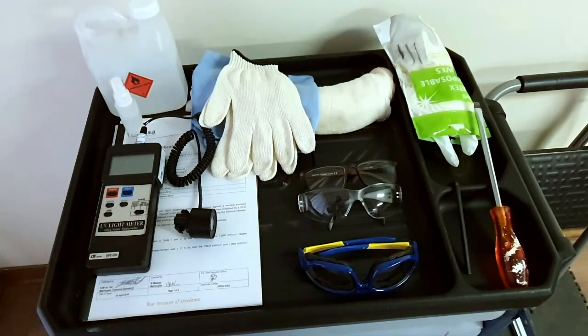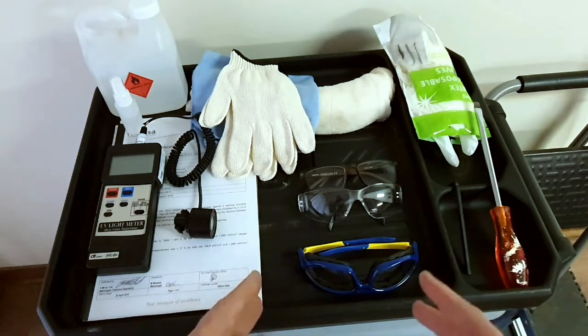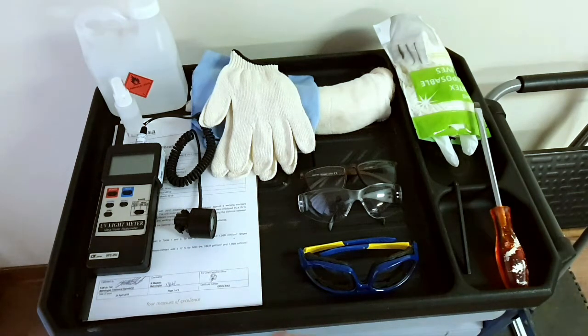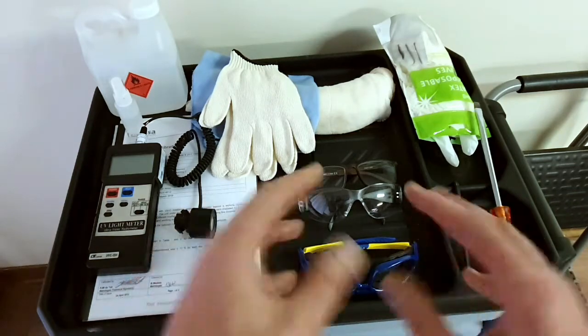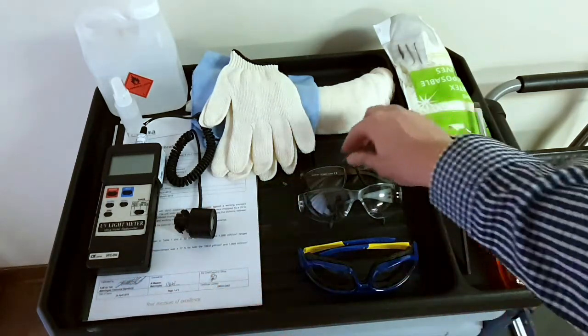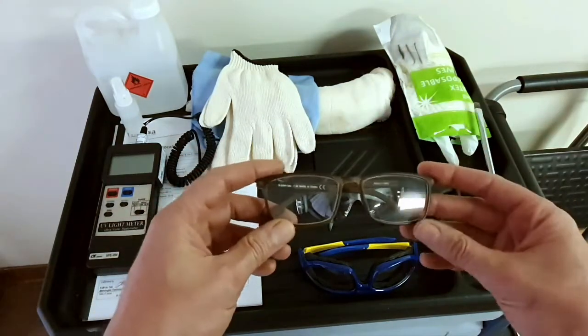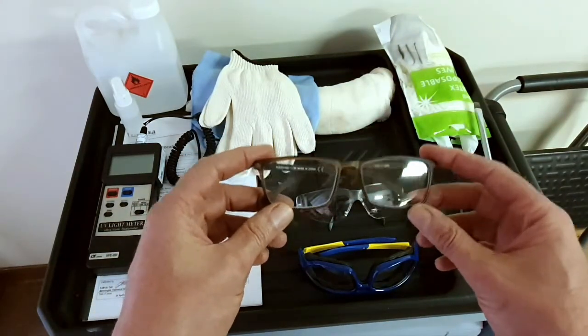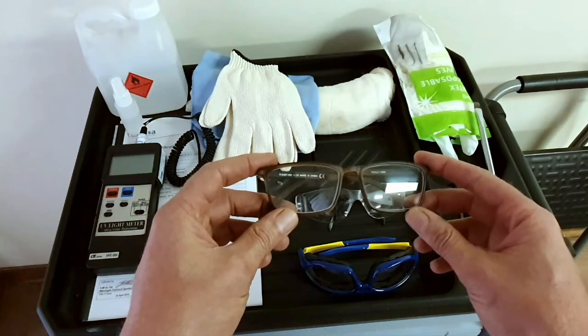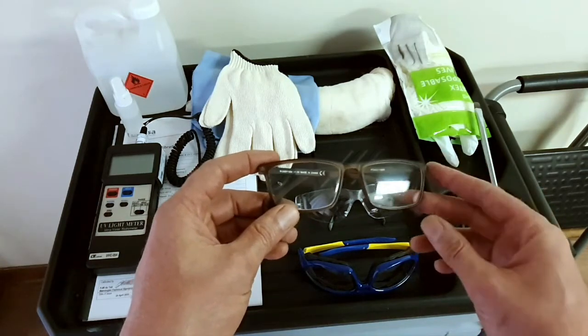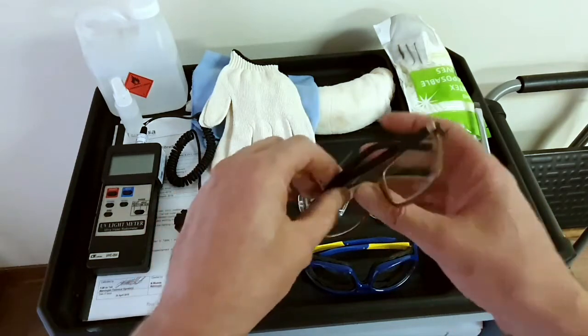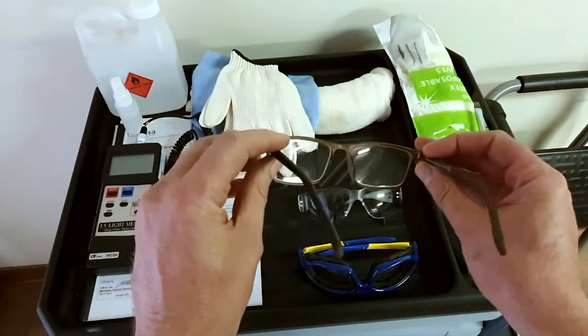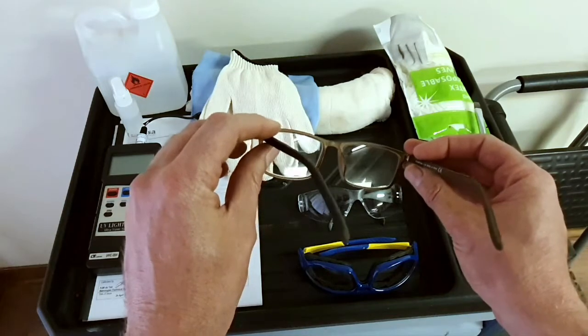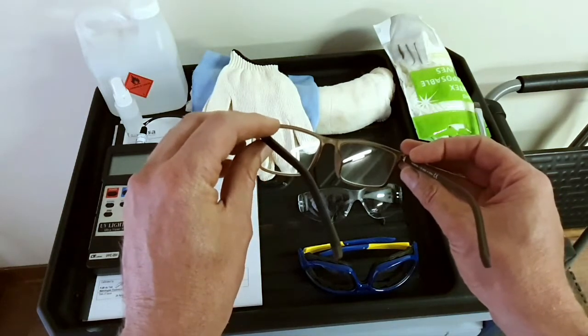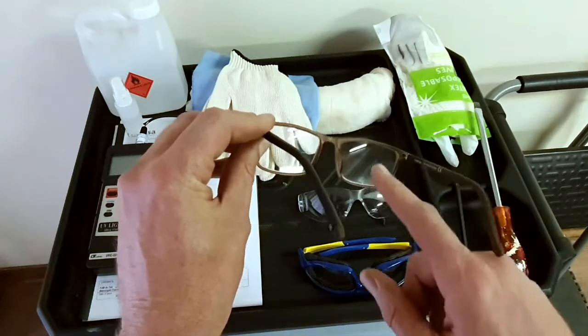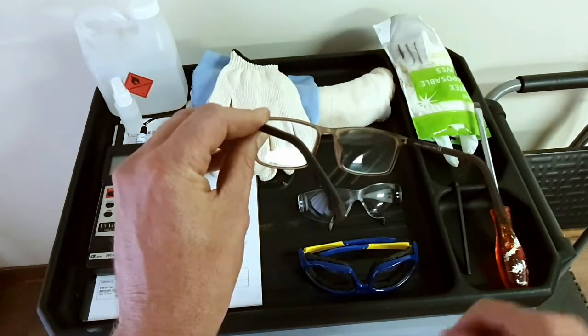And then, very importantly, is our eye protection. Especially if you're going to be working in the upper room. The device should be off while you're working in the upper room, but you can never be too safe. Please, even though UVC cannot pass through glass, eyeglasses are not safe. You can see from these eyeglasses that the light is reflecting off the glass. So what happens is, when you're wearing them, they're highly reflective to UVC, and I have heard of people receiving some eye irritation from that reflection that you get on the inside of the glasses from light behind you.